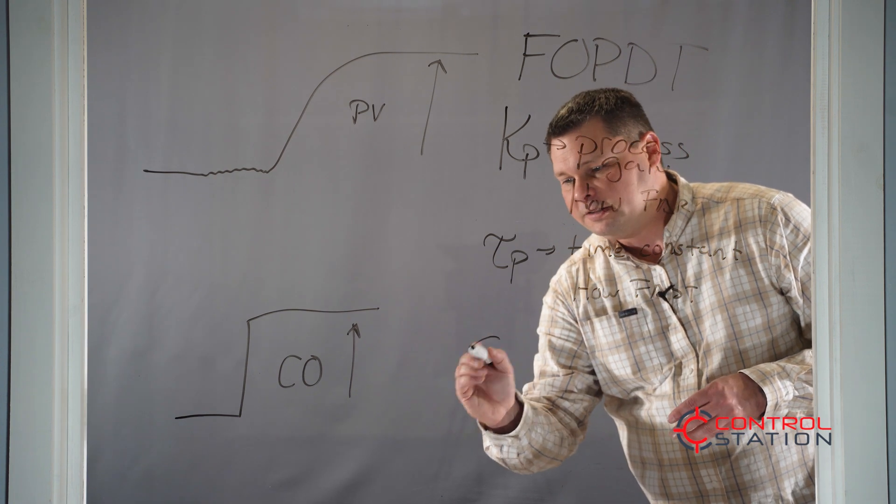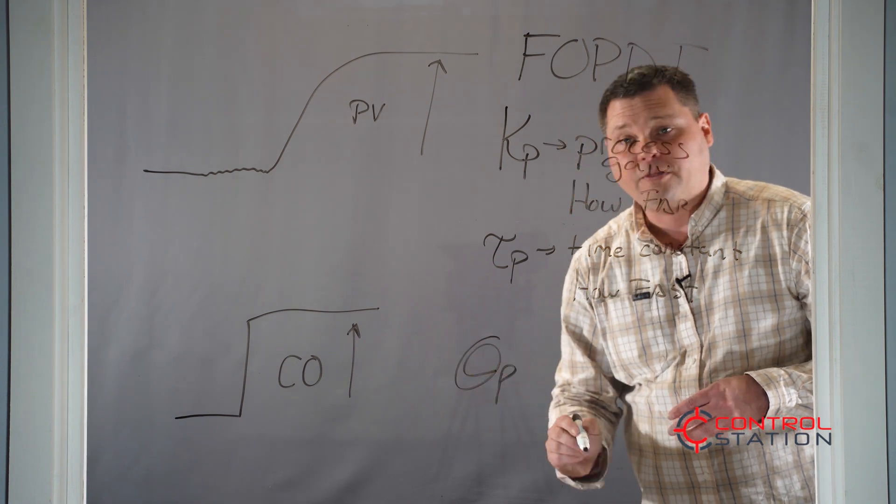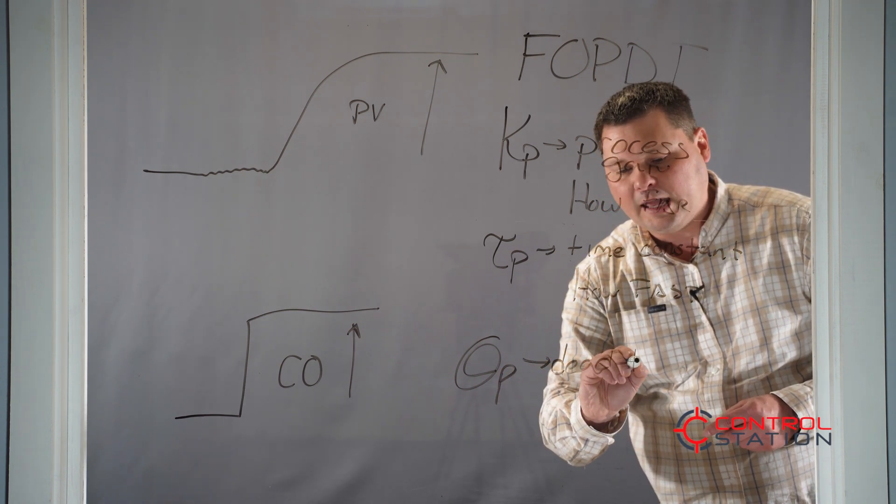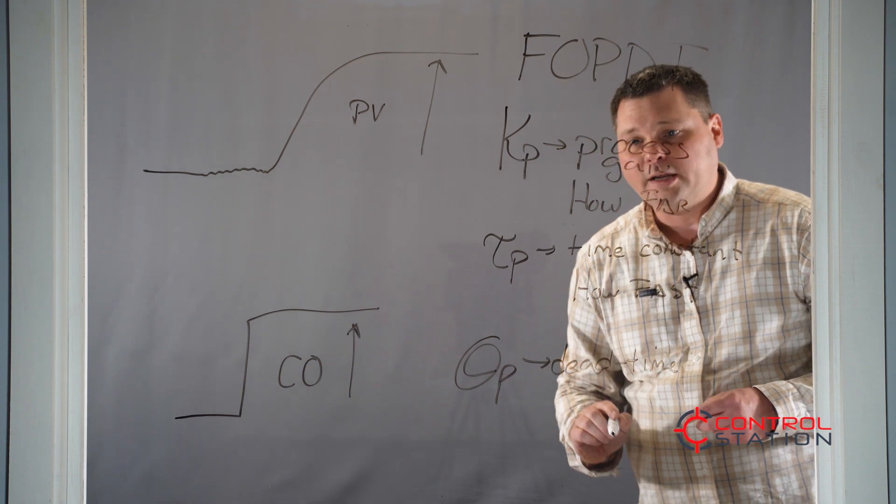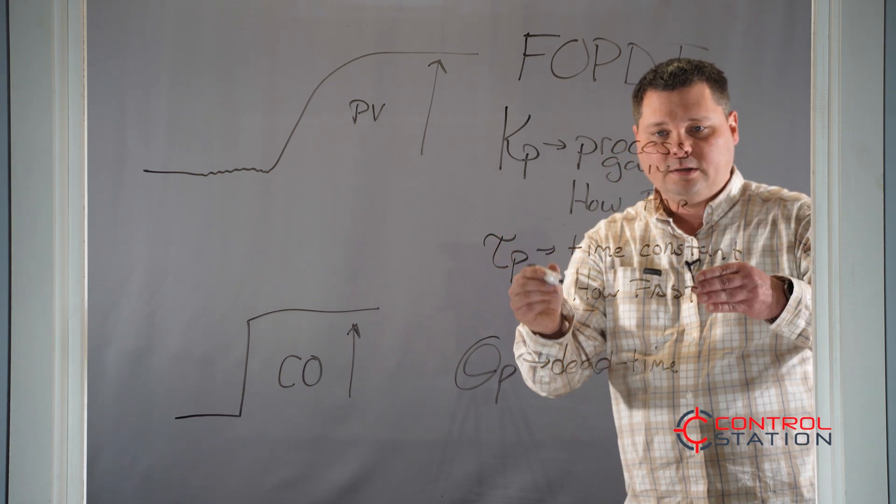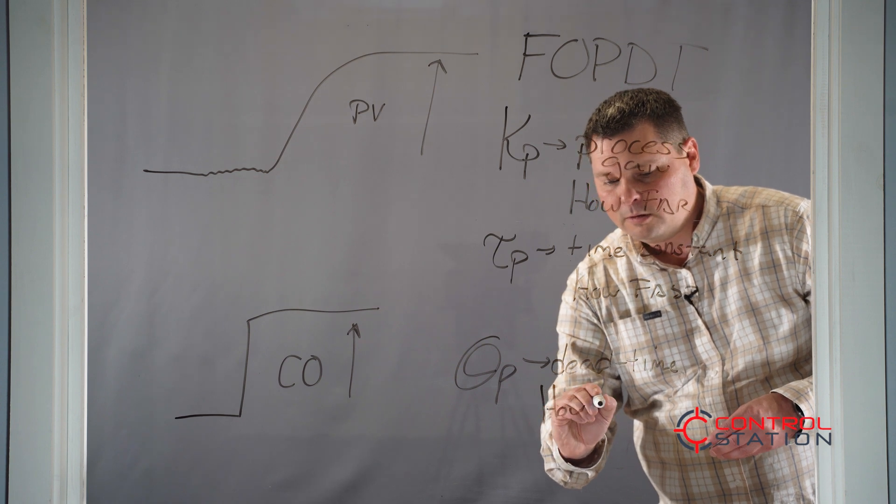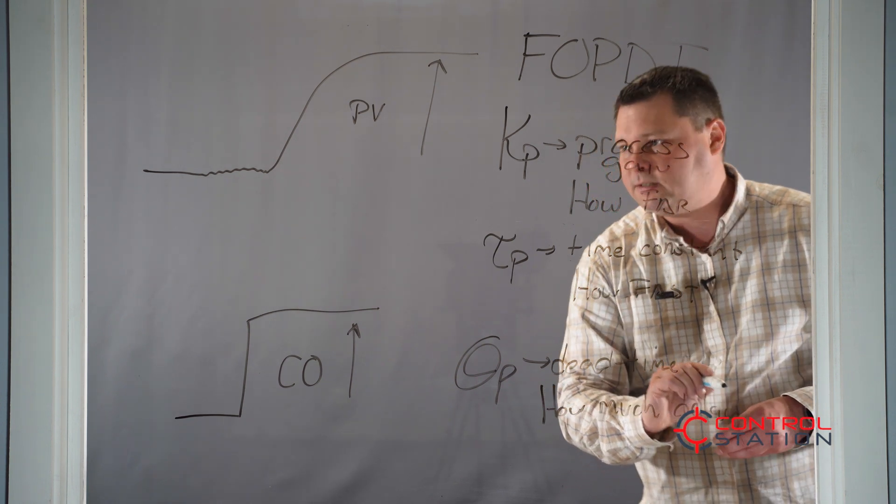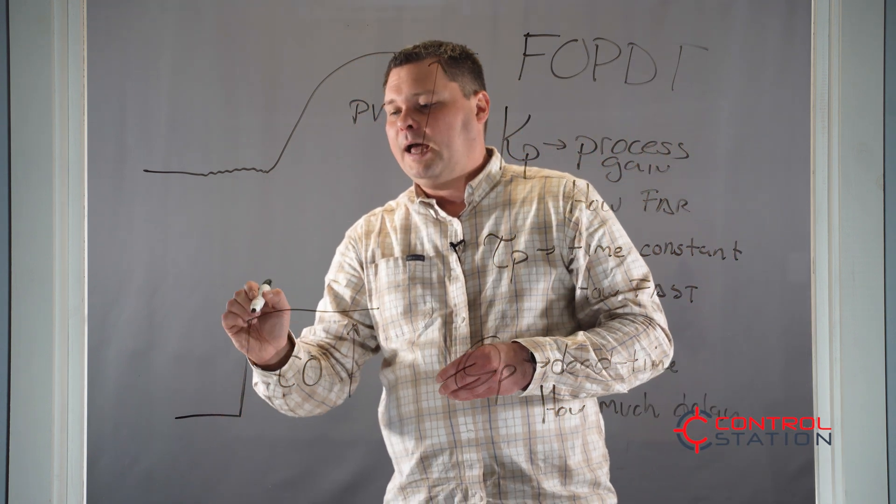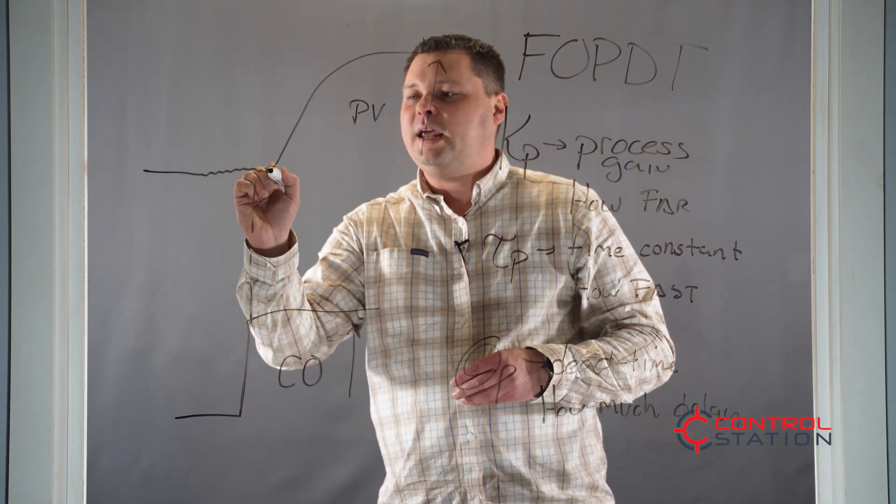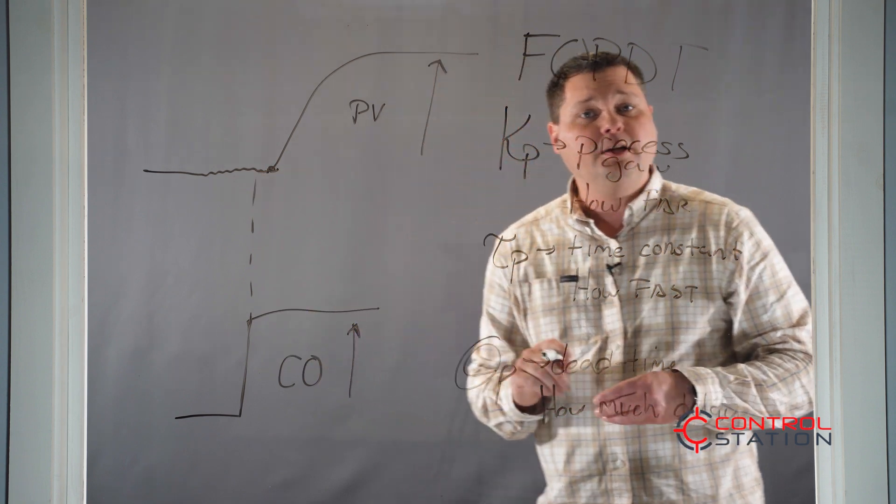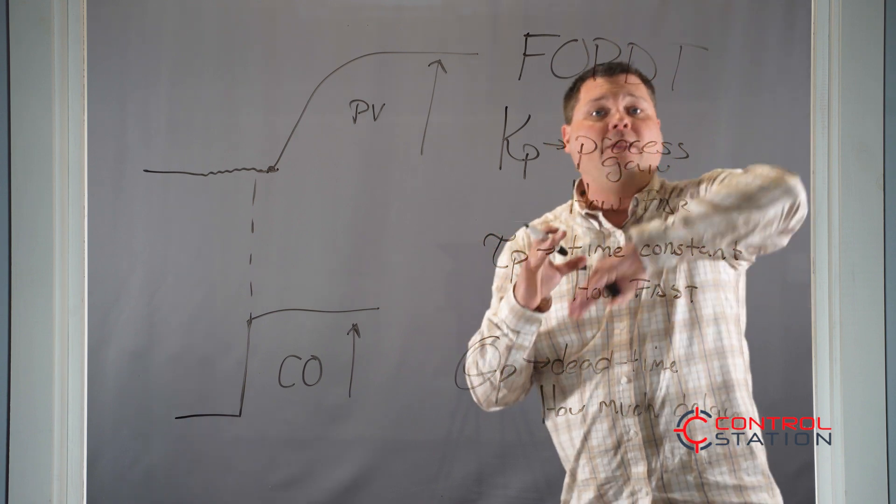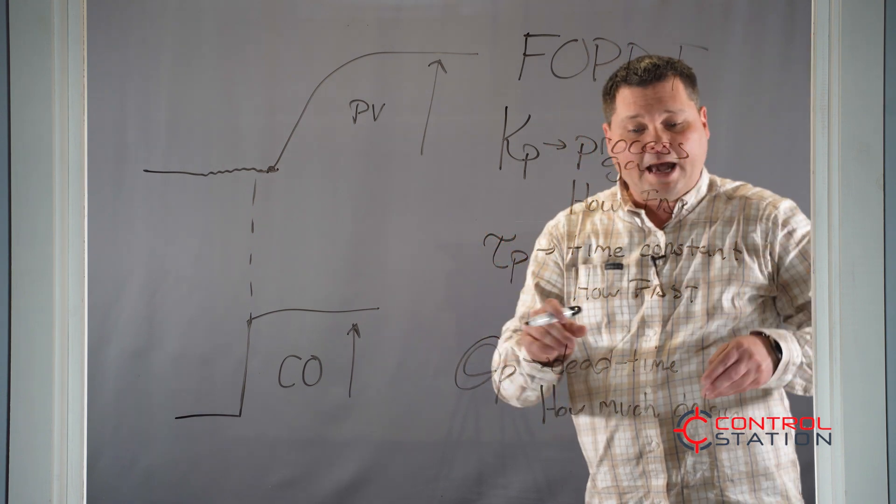The next parameter is our dead time or theta P. Our dead time is related to the delay of the system. So how fast, how far, how much delay. That's going to tell us when I make a change to my valve, how long does it take till something actually starts to happen? You open the control valve, nothing happened, nothing happened, then the flow responded, then the temperature responded. That's going to be delay.